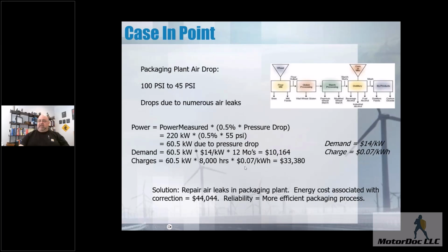So that would be at 7 cents per kilowatt hour, which was what they were paying. That's 33,380. So that comes out to be about 43,500 per year, just to feed air leaks. Now these will be both audible and inaudible.